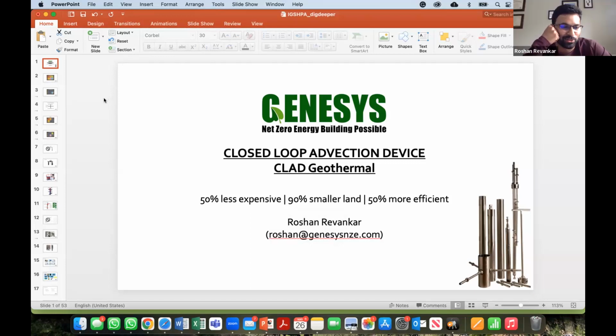So again, it was based on what we hate to call rules of thumb here in the US. I see Gerald McLean here on the call as well. Most of the people who are on this call know where the 200 feet per ton came from. It was from one small solar building at Oklahoma State campus where it so happened to be 200 feet per ton. And unfortunately, that became the industry norm of 200 feet per ton, which I know a lot of people on this call are still trying to deal with. That was just something that the guys picked up 15 years ago, that 200 feet per ton would have been the norm. But it is not the norm. Do not design your systems assuming it's 200 feet per ton. Don't design it that way.